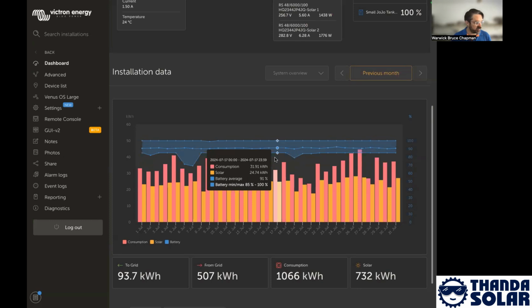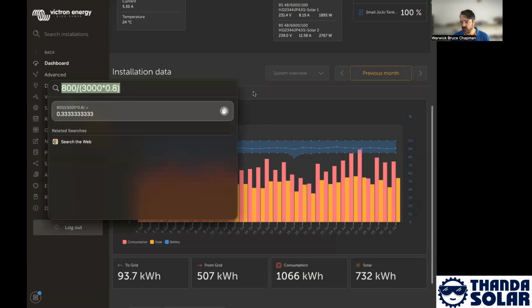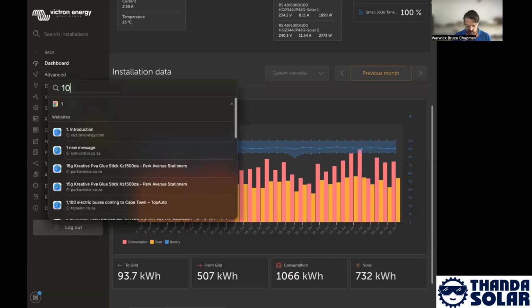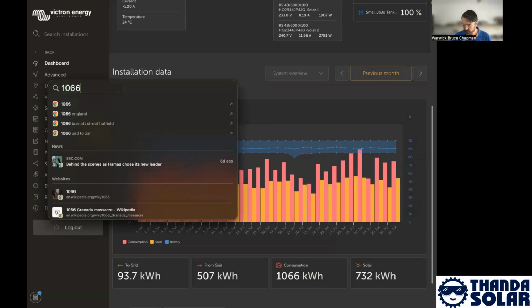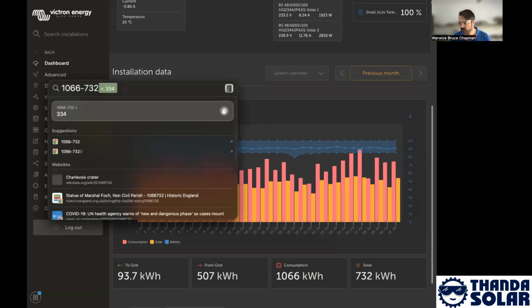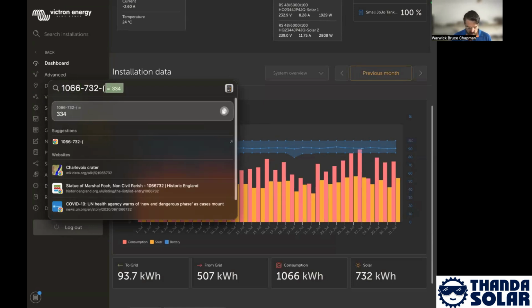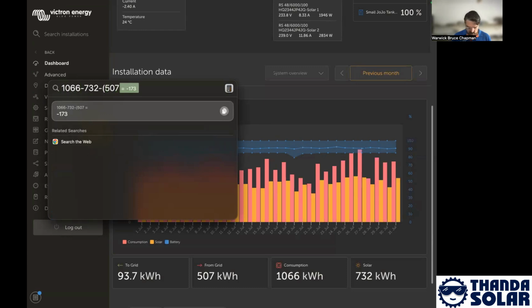So we said the multi-RS was the high frequency switching technology that's more efficient, generates better output power, and should have fewer losses. So on a sample of one site versus another, which is certainly not representative, but it tells us something, let's have a look at this. So for July, this particular site consumed 1,066 kilowatt hours, and 732 of that came from solar, and 507 kilowatt hours came from the grid, right?